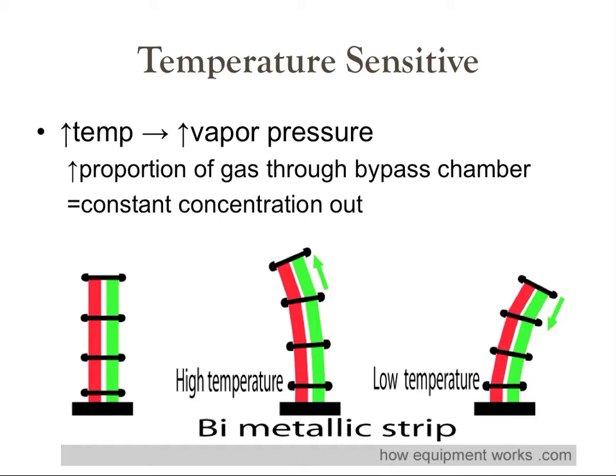When vapor is generated, it takes heat from the liquid and its surroundings, and so that heat energy is lost. When that heat energy is lost, the temperature of the vaporizer and liquid decreases, which decreases the vapor pressure of the anesthetic, which decreases the vaporizer output unless a compensatory mechanism occurs. And that's what this temperature method does.